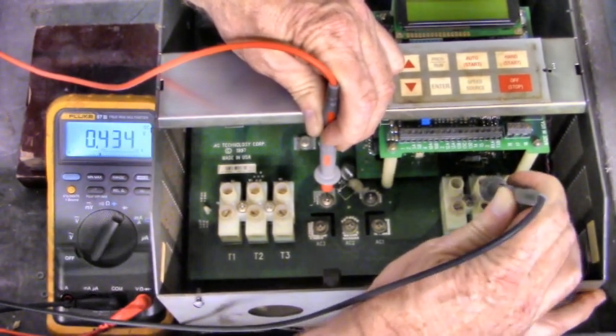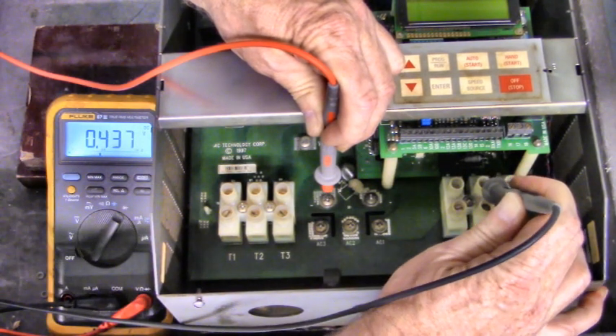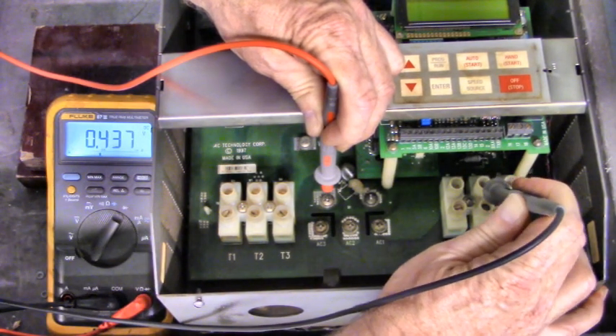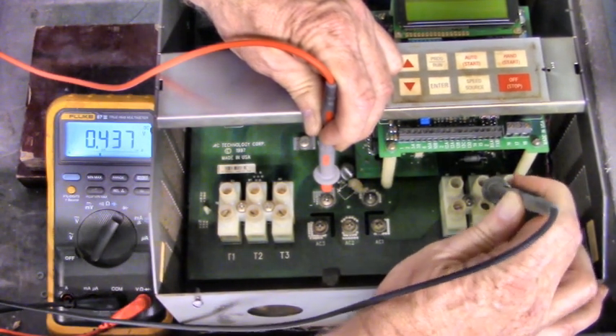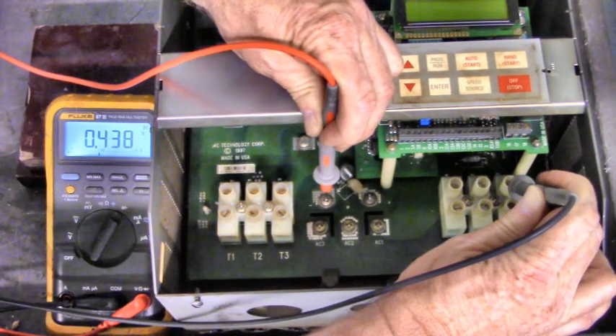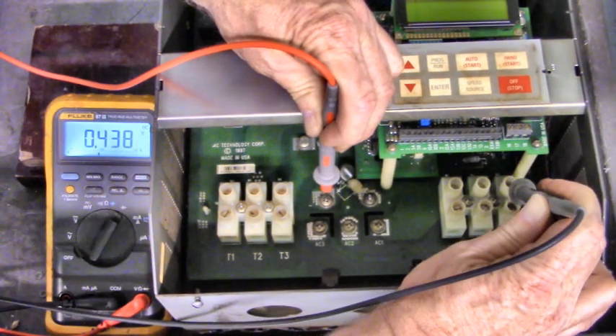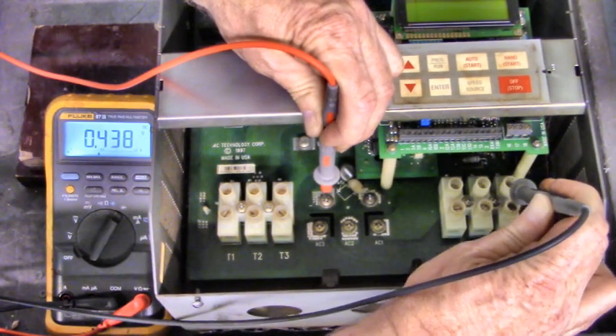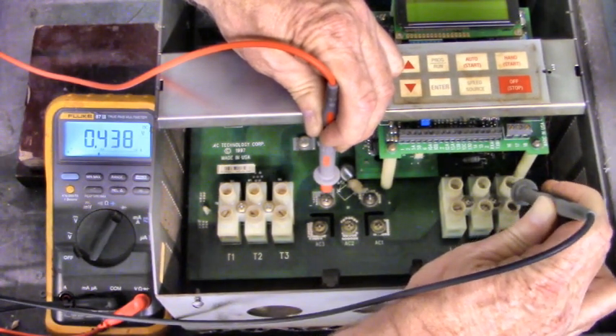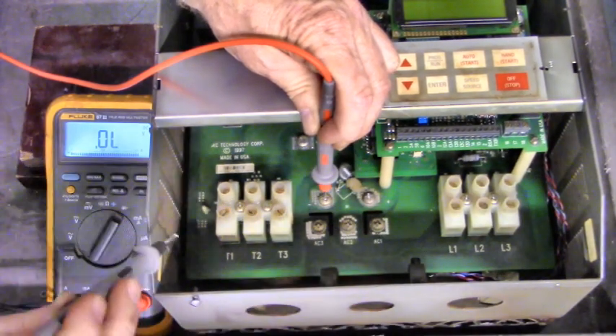Black lead to L2. .437 volt diode drop. .438 volt diode drop on L3. The three-phase bridge is good.